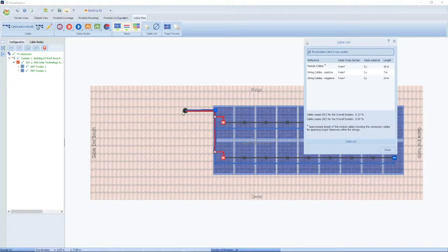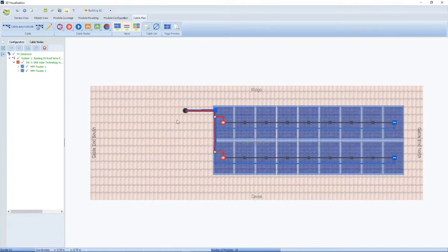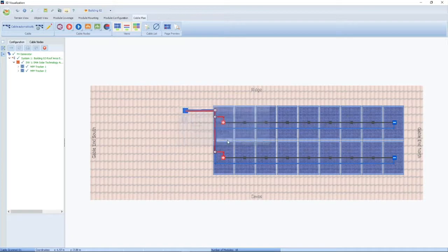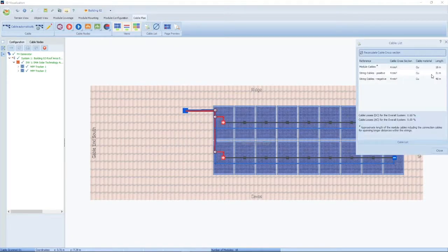The nice thing about the cable plan is it tells you how much cable you need. You can right-click on the grommet and edit it to tell it how far the grommet is from the inverter — let's say 12 meters. If you click on the cable list, it will add the 12 meters to the strings, showing you need 31 meters of positive cable and 48 meters of negative cable.